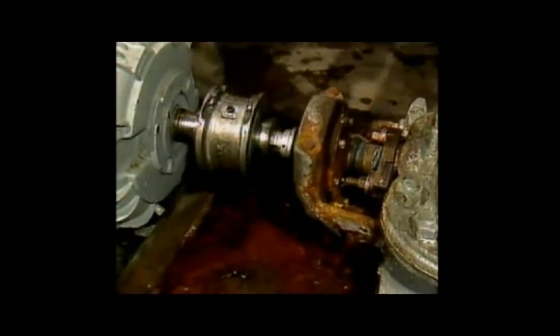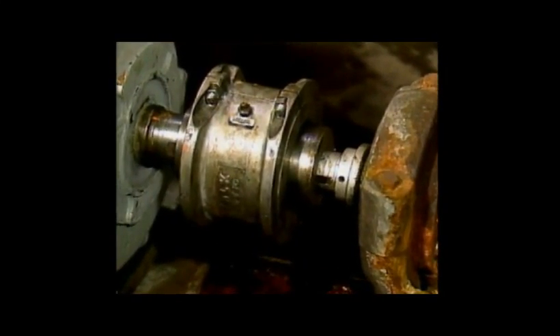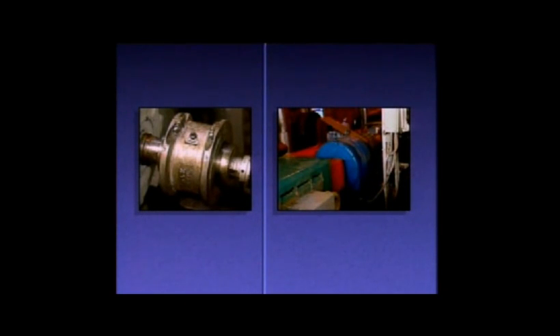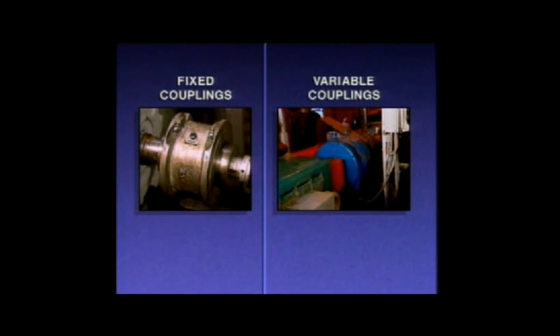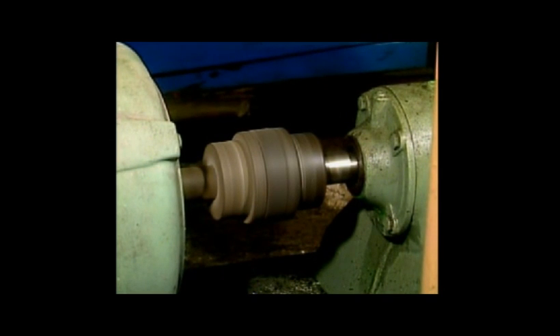Another piece of auxiliary equipment is a coupling — a device that connects the driver's shaft to the pump shaft. Couplings can be divided into two categories: fixed couplings and variable couplings. When a fixed coupling is used, the speed of the pump is fixed by the speed of the driver, so to change pump speed, the driver speed must change. When a variable coupling is used, the speed of the pump can be changed without changing the speed of the driver.